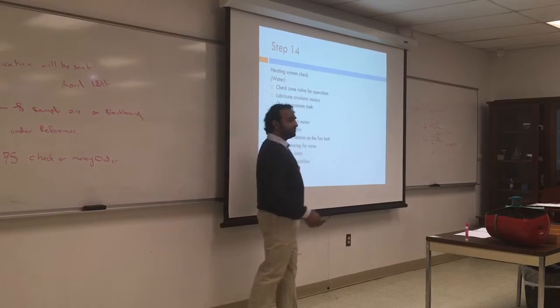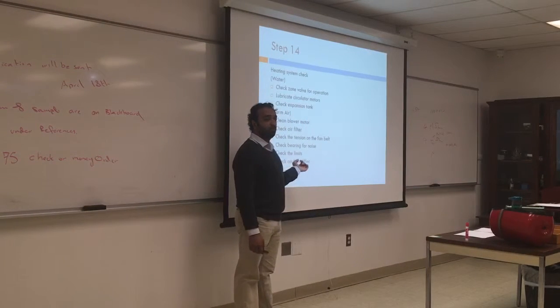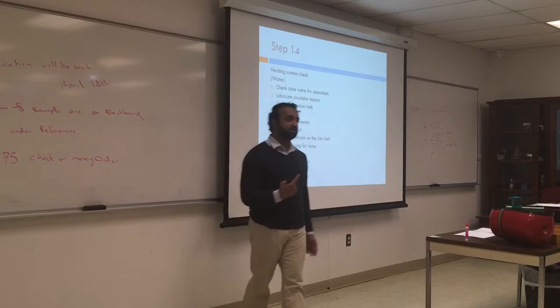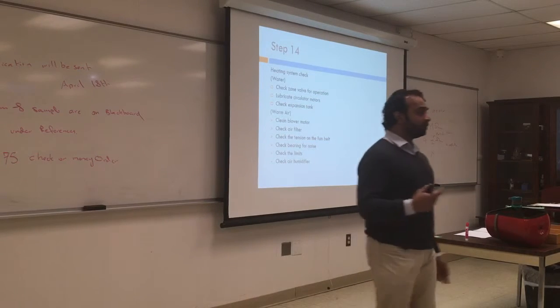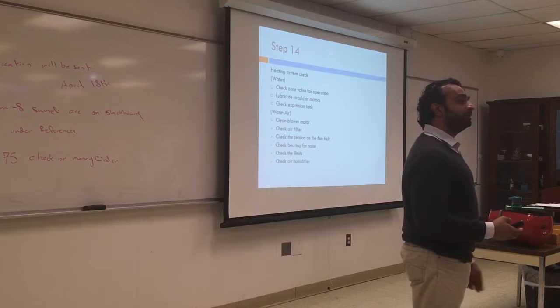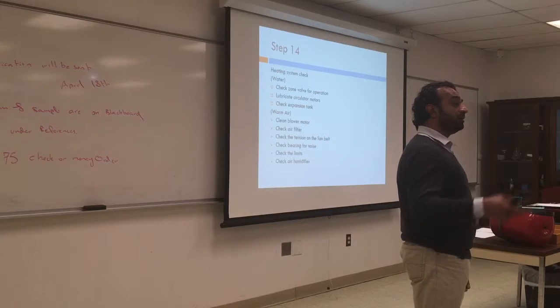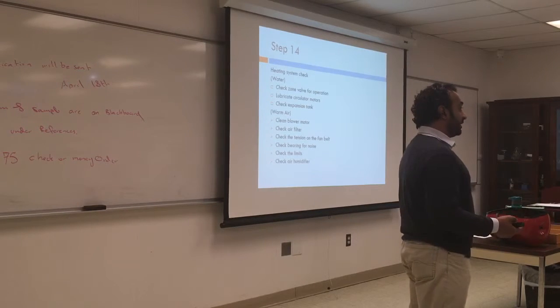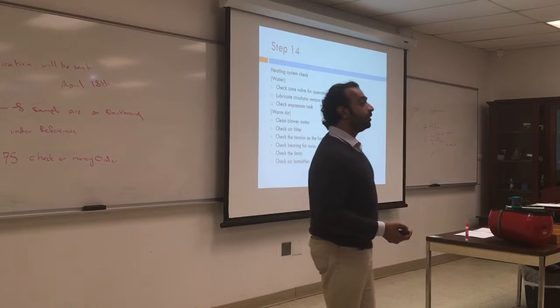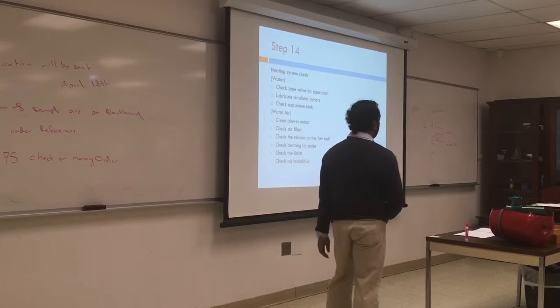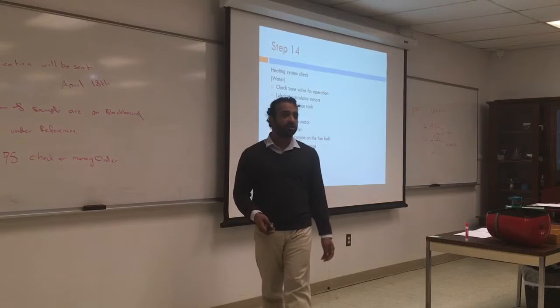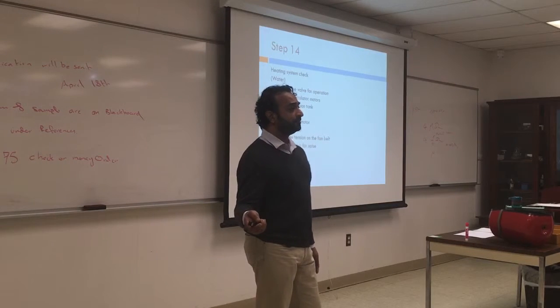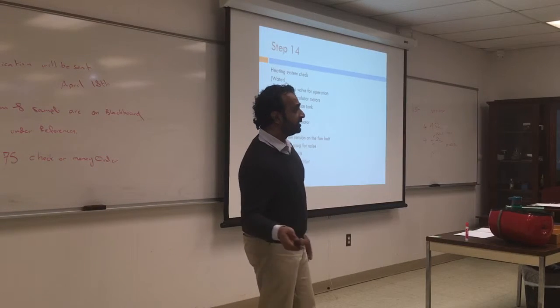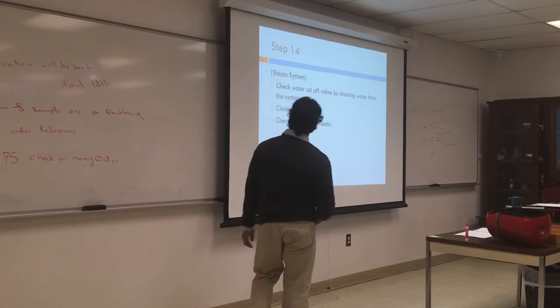If there's a humidifier, check for the water connection. Sometimes in that system they put a humidifier that will dispense some water, and this humidifier needs to be connected to the water supply, otherwise it's not going to get water. And also, if the warm air system is coupled with air conditioning, check the condensate pump function, which is running and it's draining water to the outside.